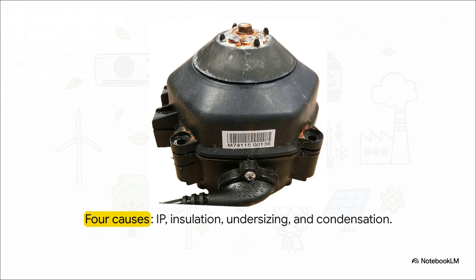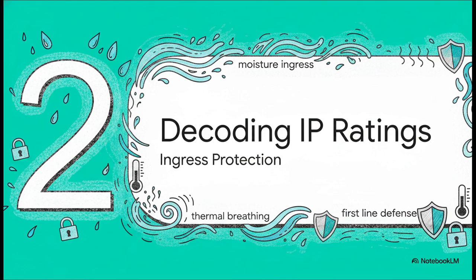Second is a low insulation class. Cooling tower motors are running under continuous load, and your standard Class B insulation usually just doesn't have the thermal margin compared to Class F or H. Number 3 is undersizing, which jacks up thermal stress and completely slashes the service life. And finally, condensation hitting the bearings. See, temperature swings cause internal moisture cycles, what we call thermal breathing, and that just tears through lubrication and accelerates bearing wear like crazy. Okay, so how do we actually stop that moisture ingress and thermal breathing?